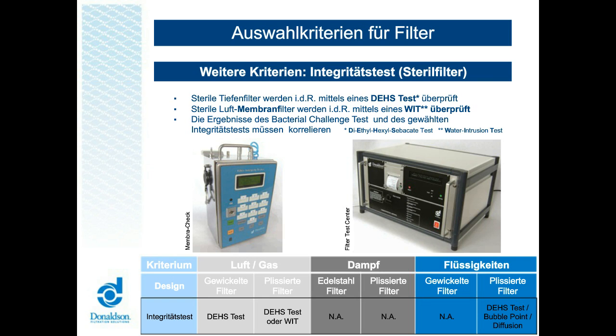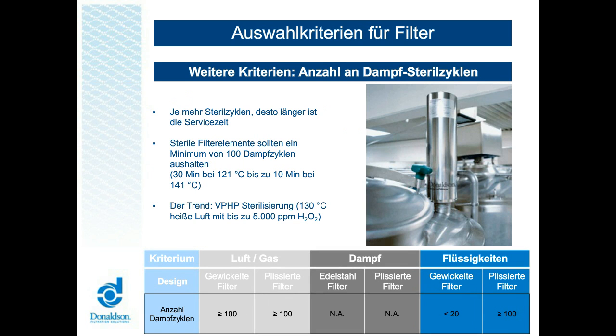Der nächste Punkt ist die Anzahl an Dampfsterilzyklen. Als Faustregel gilt: Je mehr Sterilzyklen ein Filter aushält, desto länger die Servicezeit und desto geringer die laufenden Kosten. Als Maßstab gilt, dass jedes Filterelement — egal ob im Luftgas- oder Flüssigbereich — ein Minimum von 100 Dampfzyklen aushalten sollte: entweder 30 Minuten bei 121 Grad Celsius oder 10 Minuten bei 141 Grad Celsius. Bei gewickelten Filtern im Flüssigbereich liegt die maximale Anzahl an Sterilzyklen im Allgemeinen bedeutend niedriger, im Bereich von 10 bis 20 Zyklen.